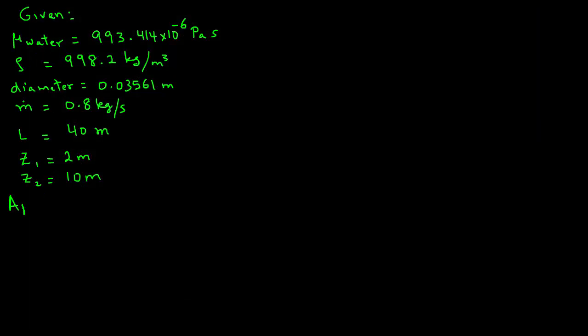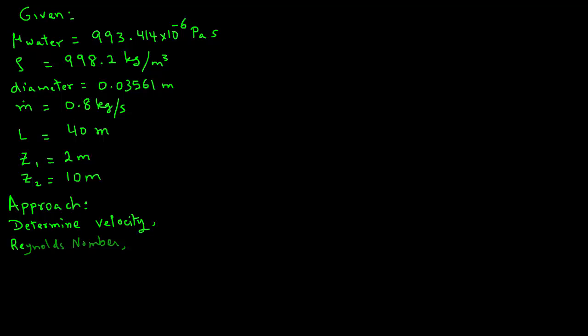Our approach will be to first determine the mean velocity of water in the pipe, then calculate the Reynolds number, and from the Reynolds number use an appropriate diagram to find the friction factor. Then we will use the energy equation developed in previous tutorials to determine the power requirement for the pump.